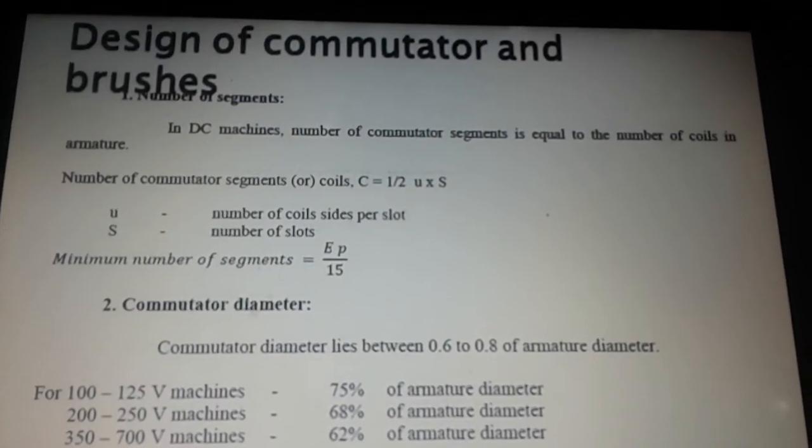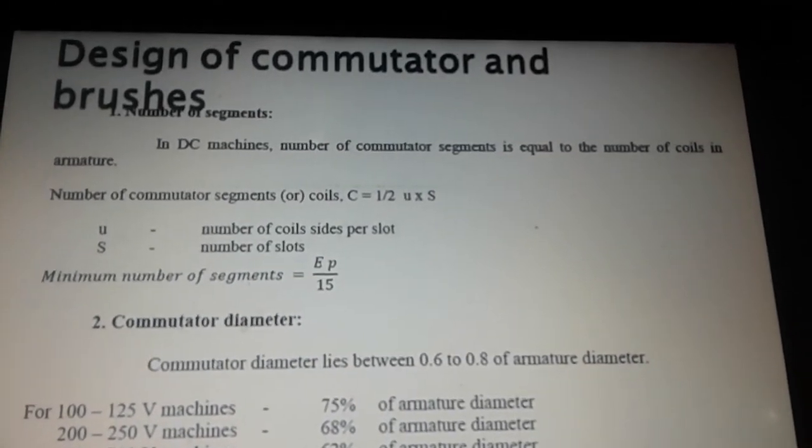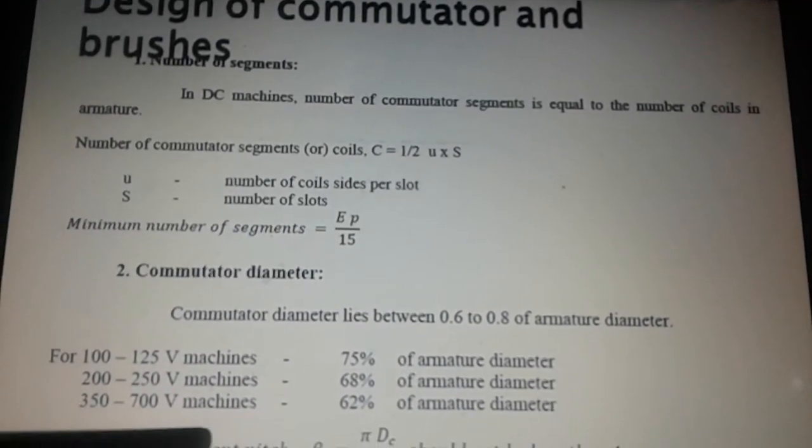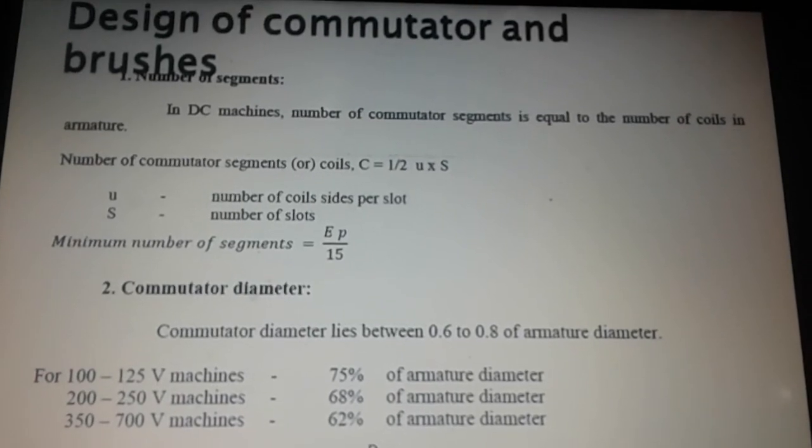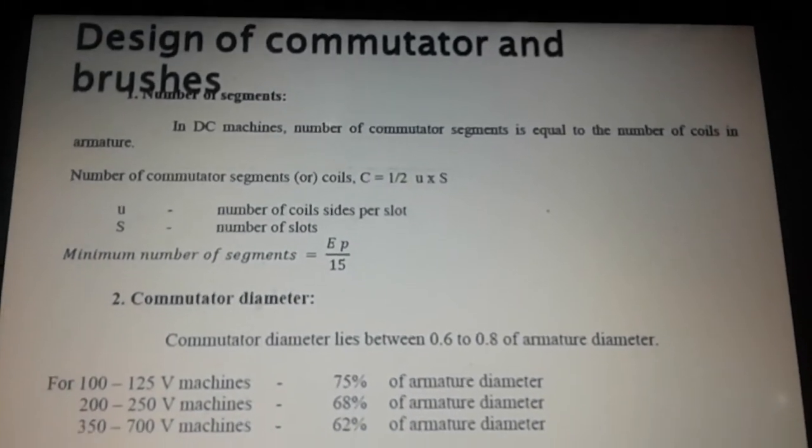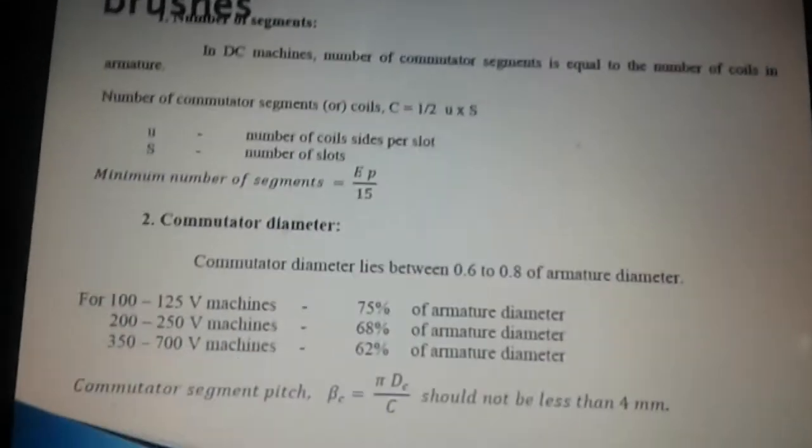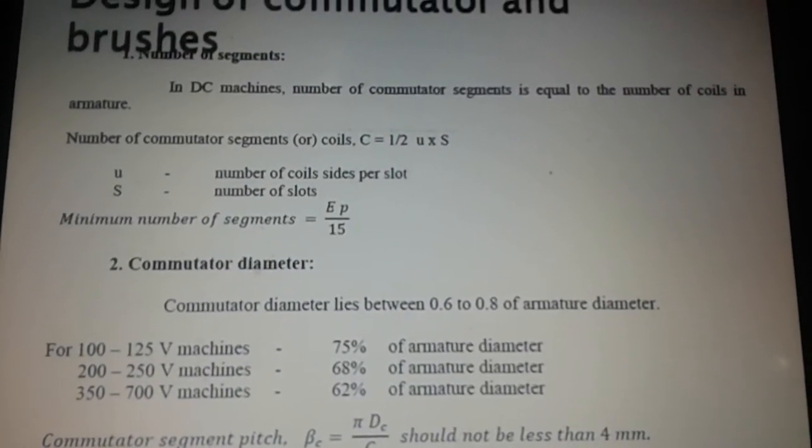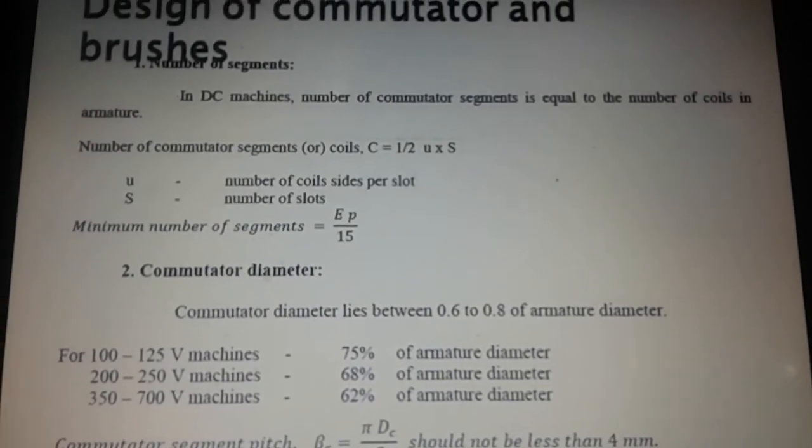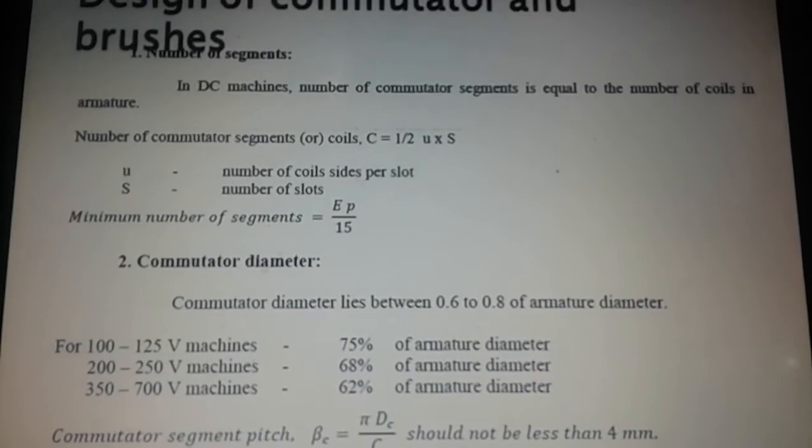For 200 to 250 volt machines, it is 68% of armature diameter. And for 350 to 700 voltage machines, it is 62% of armature diameter. The commutator segment pitch is πDC divided by C, and it should not be less than 4 mm.